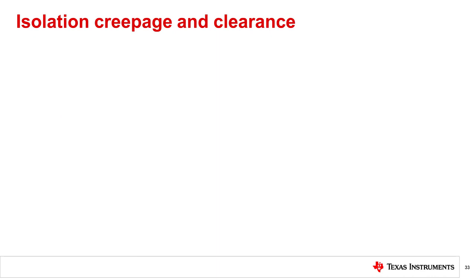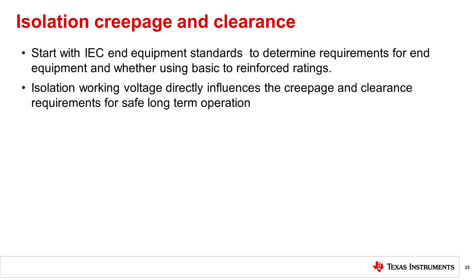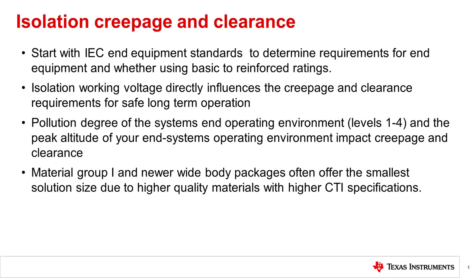This concludes our introduction to isolation, creepage, and clearance. We outlined a general set of guidelines to follow when determining creepage and clearance requirements. These include understanding the required insulation rating of basic or reinforced for your end equipment — IEC equipment standards are the most common starting point, and creepage requirements may double from basic to reinforced. Identify the insulation working voltage of your system, as this will directly influence the creepage and clearance requirements to maintain safe, long-term operation with minimal risk of electrical failure or arcing. Identify the pollution degree of the system's end operating environment (levels 1 through 4) and the peak altitude. Finally, consider the material group category of the isolator being used — newer wide-body packages often offer the smallest solution size due to higher-quality materials and higher CTI specifications.